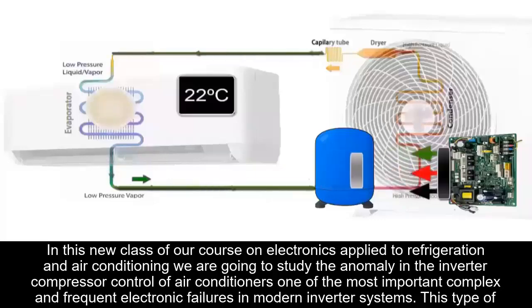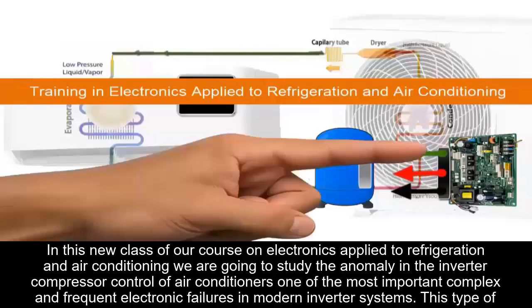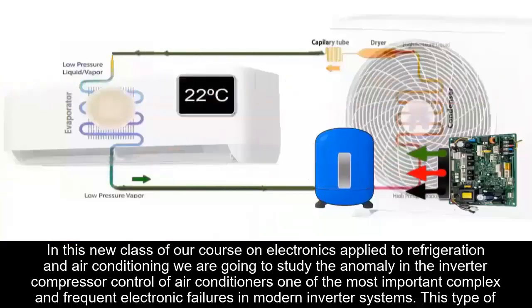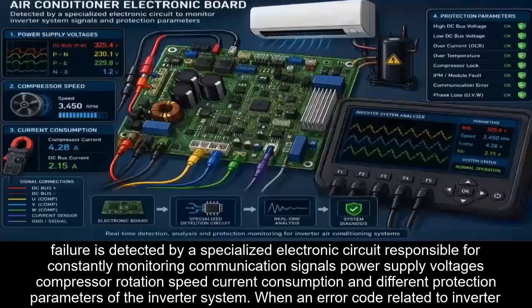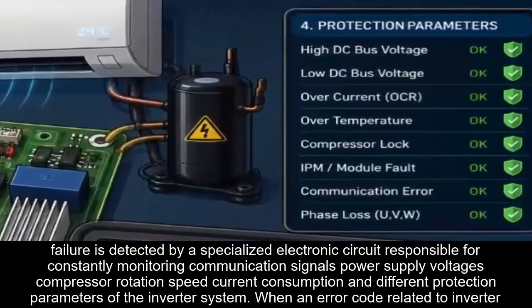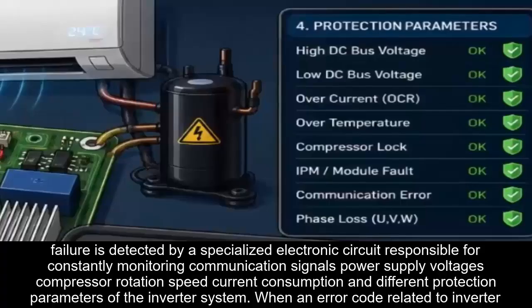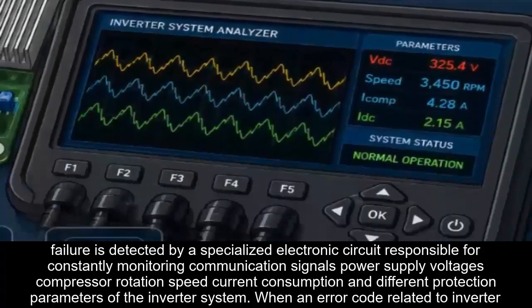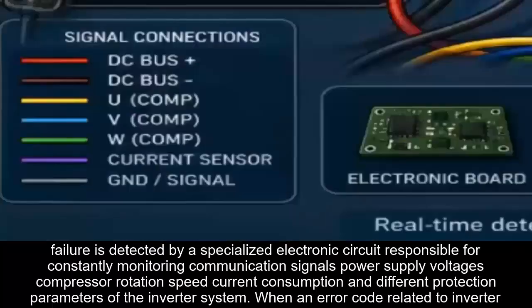In this new class of our course on electronics applied to refrigeration and air conditioning, we are going to study the anomaly in the inverter compressor control of air conditioners, one of the most important, complex, and frequent electronic failures in modern inverter systems. This type of failure is detected by a specialized electronic circuit responsible for constantly monitoring communication signals, power supply voltages, compressor rotation speed, current consumption, and different protection parameters of the inverter system.